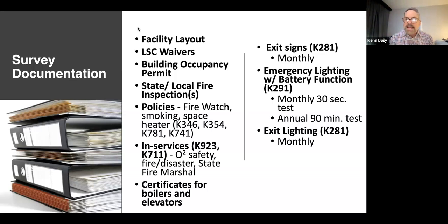And then you have your monthly exit sign auditing. Exit signs should be audited every month to make sure that they are not damaged, they're in place, and that they're working. And then, of course, you have emergency lighting and emergency battery operated lighting. I know in your top 10 was K-tag 291, which, when it says emergency lighting, is the one with the battery in it. I think the most common citation is where maintenance is not testing those at the correct frequency, which is once a month: you push the button on the side and make sure it's operating for 30 seconds under battery power. And then once a year, you have to test it for 90 minutes. You may have to push it or duct tape it down for 90 minutes to make sure it's working.